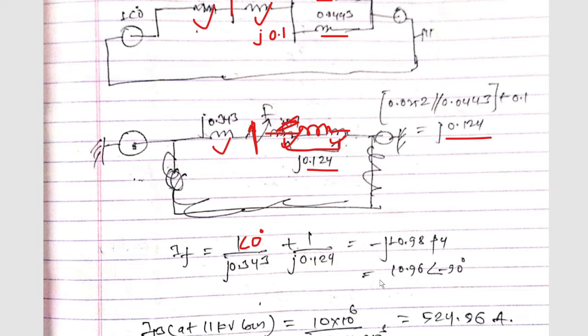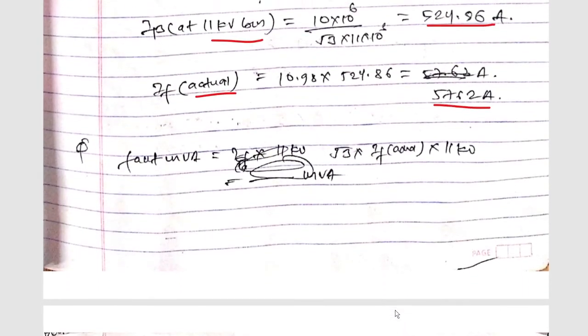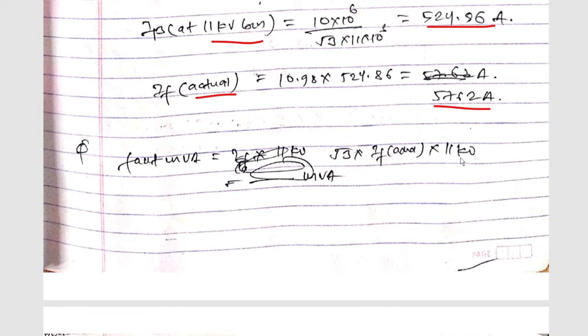The base current at 11 kV side is: 10 × 10⁶ / (√3 × 11 × 10³) = 524.86 ampere. The actual fault current = 10.96 × 524.86 = 5762 ampere. The fault MVA = √3 × If(actual) × 11 kV, so solving this gives us the fault MVA at the 11 kV bus.